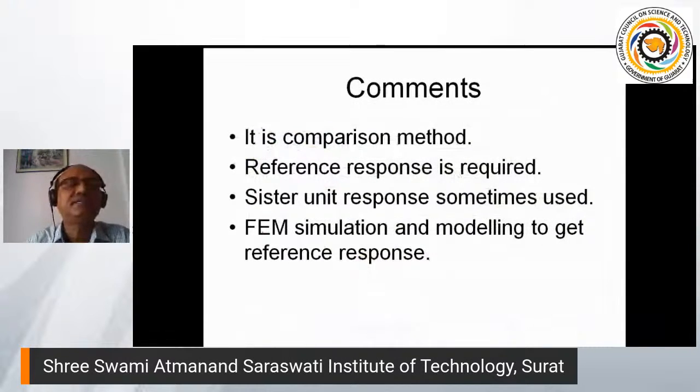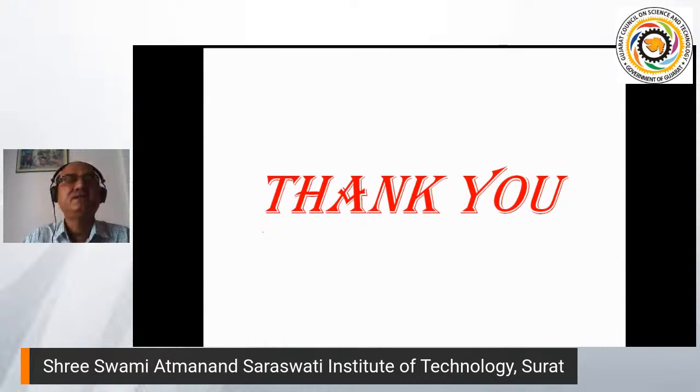It is a comparison method, and you should have a reference response for this measurement. The reference response may be taken from the sister unit or the same unit. The best one is from the same unit. If it is not available, then from a sister unit of similar design. If that is also not available, then FEM simulations and modeling can be used to get the responses. Right, so this is related to the PD measurement and SFRA measurement. Now if you have any question, you can put it.